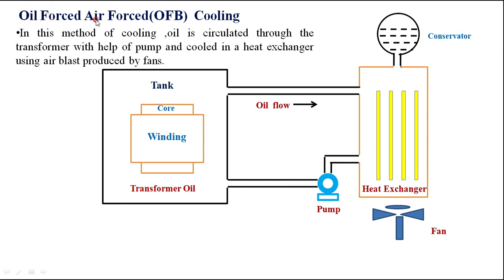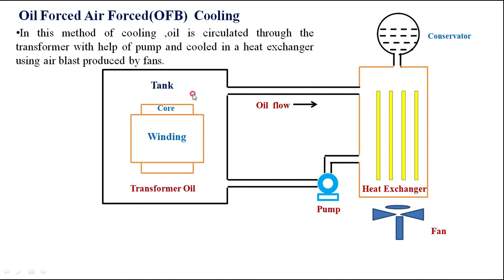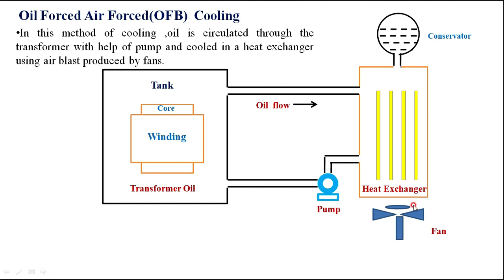The next method is oil forced air forced cooling. The improvement here is that instead of natural cooling of the transformer oil in the heat exchanger, forced air is blown onto the heat exchanger using an external fan to get a better cooling effect. In this method, oil is circulated through the transformer with the help of a pump and cooled in the heat exchanger using an air blast produced by fans.